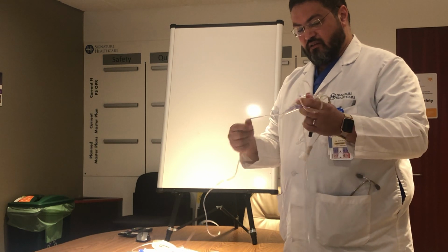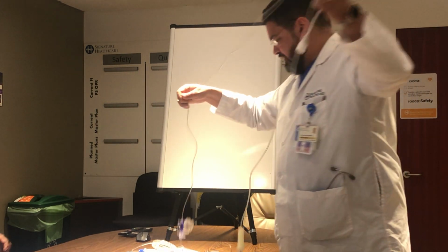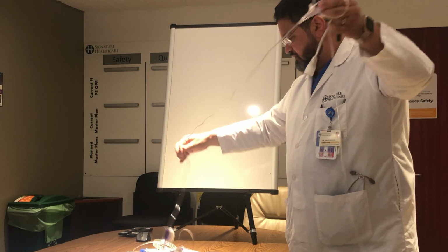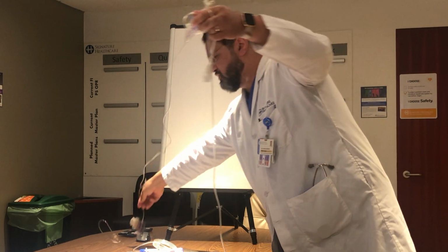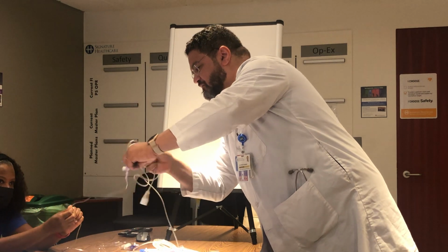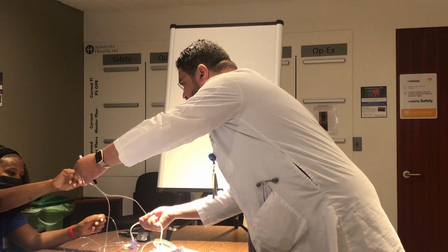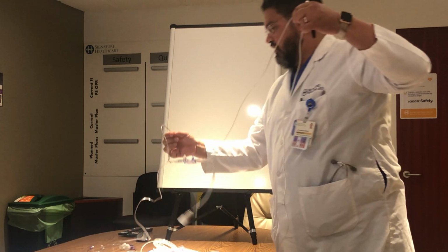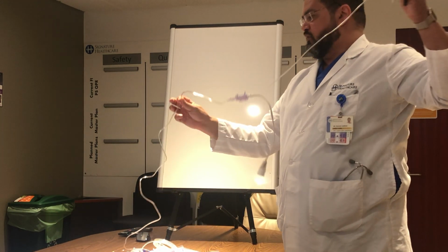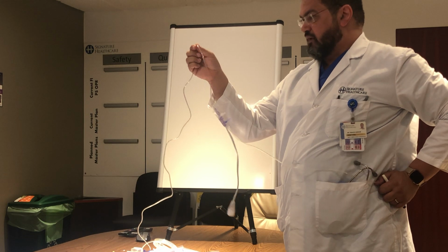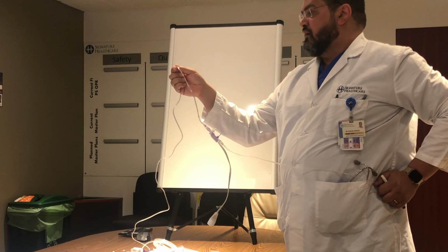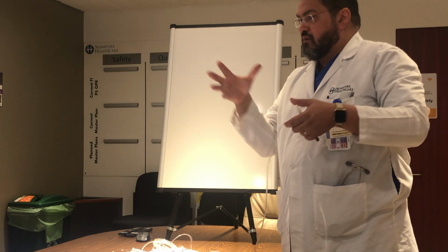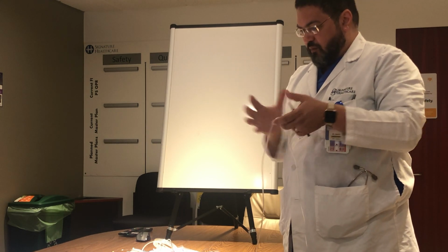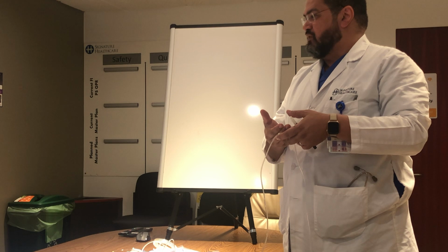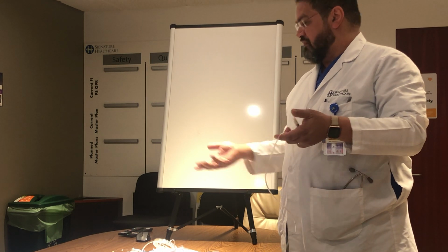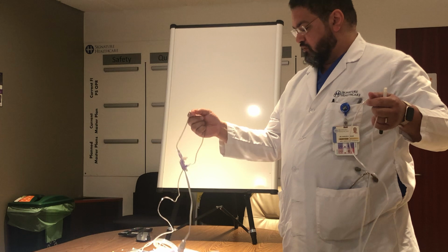Now, look at this. So right now, from the transducer down, this goes to the patient, right? Feel this tubing here, and feel this tubing. Oh, yeah. There's a huge difference, right? This is a very hard tubing, you can't compress. This is easy to compress. So this one in my hand here is called non-compliant tubing. Non-compliant tubing means that it doesn't take the pulse and just expand, like this one here, it takes the pulse and does like this. So it's not going to be good if you want to measure pressure here, it's not going to measure. This one measures pressure.